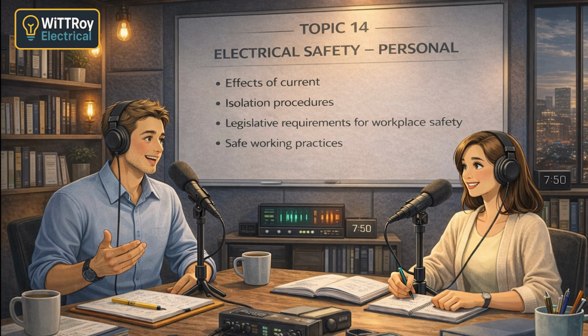And the tag goes with that. Yes, a safety tag is attached to the isolator. It shows who isolated it, when and why. It warns others not to operate it. So the tag is about communication. Exactly. Tags improve communication on site and reduce accidental energization. But the tag alone doesn't physically stop it. Right. A tag by itself does not prevent operation. Wherever possible, lock and tag together.